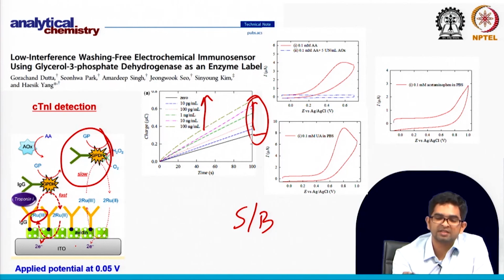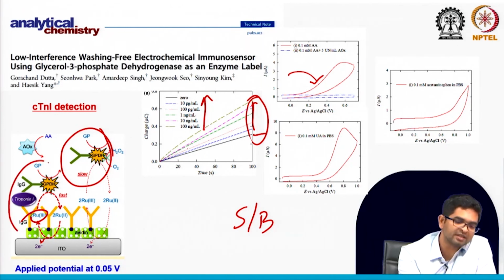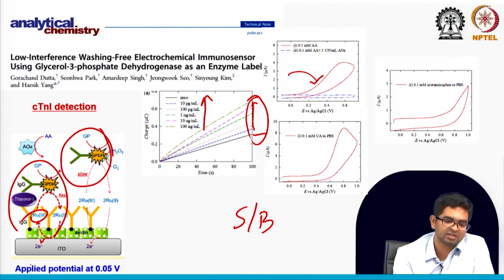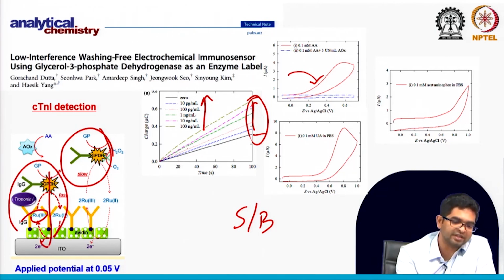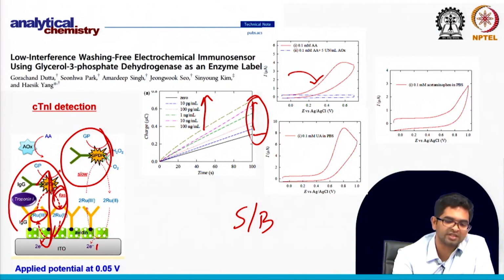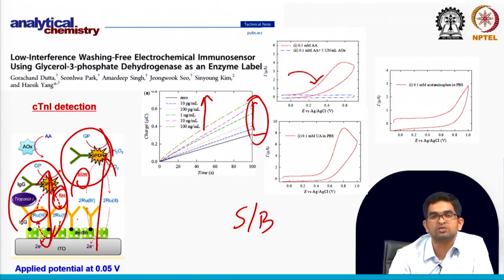We are minimizing the interfering species effect by applying a very good potential, also by optimizing the label so that we can avoid other side reactions, and we are designing a redox cycling reaction so that when the label is close to the surface, it will show very fast reactions. When they are not very close, it will show slow reactions.